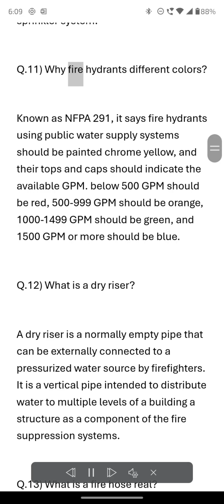Q.11. Why are fire hydrants different colors? Known as NFPA 291, it says fire hydrants using public water supply systems should be painted chrome yellow, and their tops and caps should indicate the available GPM. Below 500 GPM should be red, 500 to 999 GPM should be orange, 1000 to 1499 GPM should be green, and 1500 GPM or more should be blue.